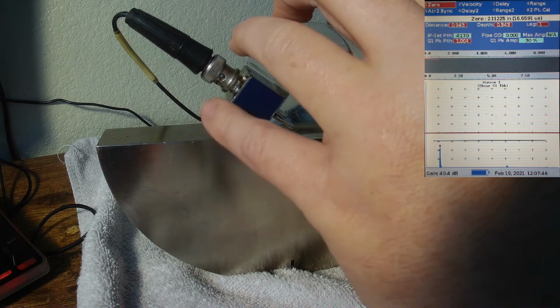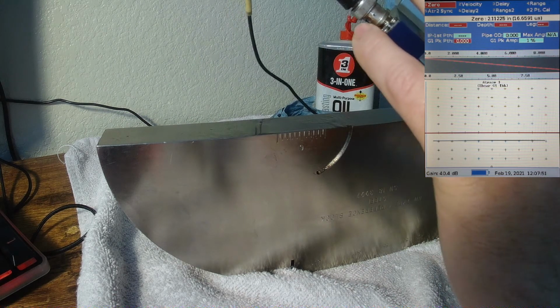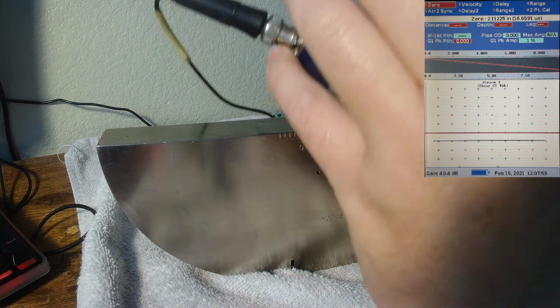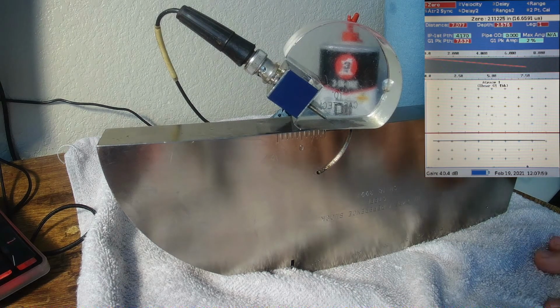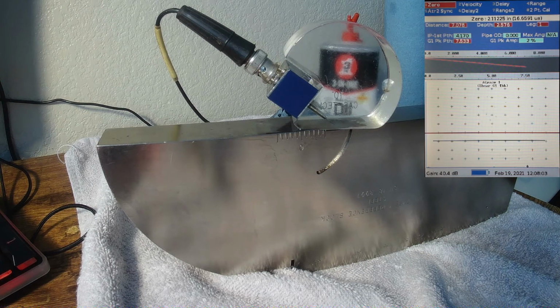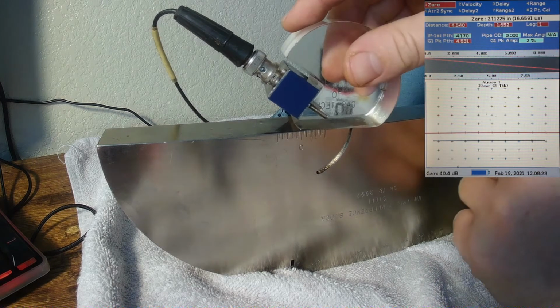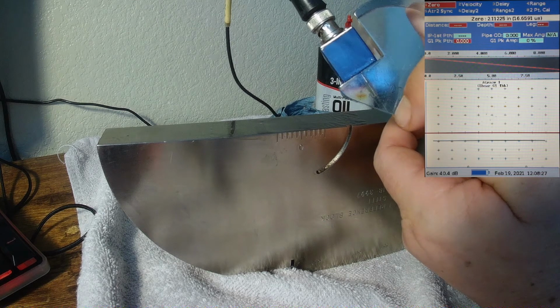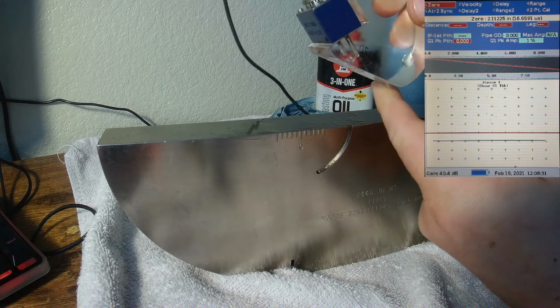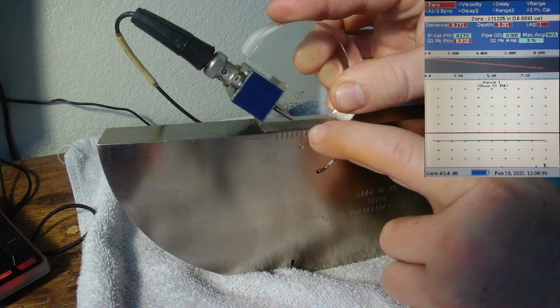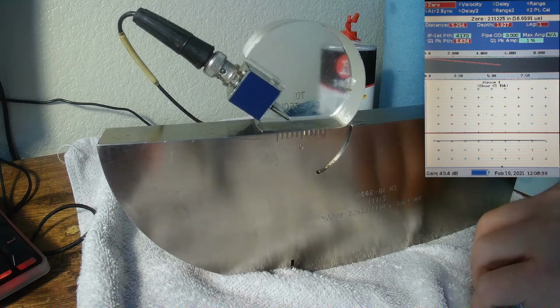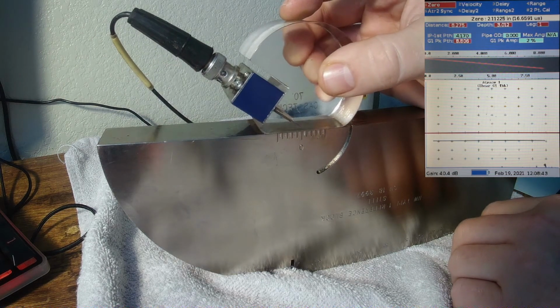So the 0 that this machine shows, as you can see right there, it shows the actual inches of offset that you're doing. And then in parentheses is the microseconds, the US, which is on the Krautkramers, the delay or 0, the probe delay. It just shows it in microseconds. So it'll always be somewhere around there. And what you're doing is you're essentially taking out this area where it's traveling through, nothing that we care about. So the actual 0 start point is at the interface. And so that's what we're trying to verify. Otherwise, all your dimensions are going to be off.